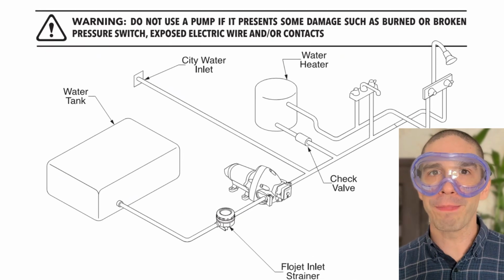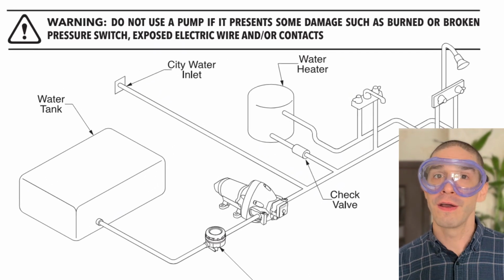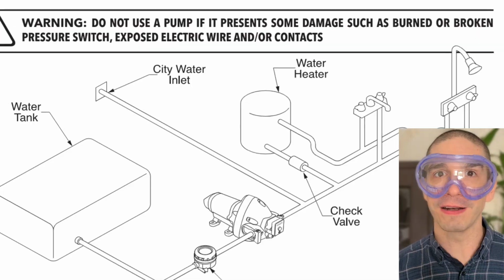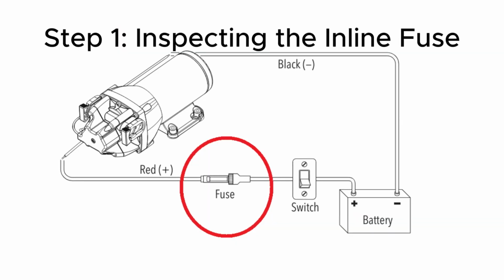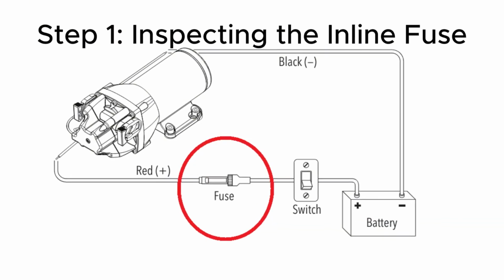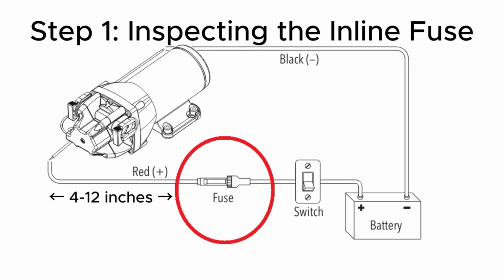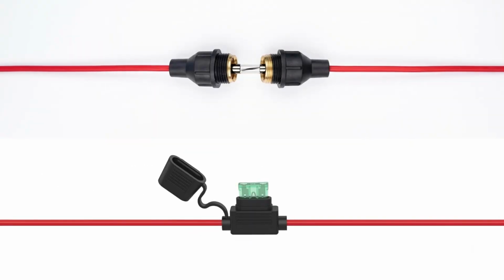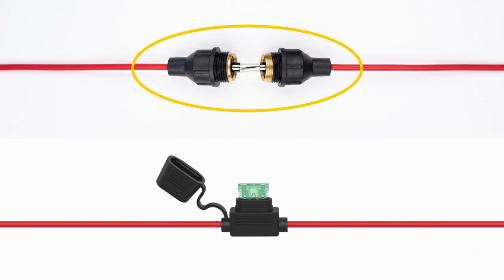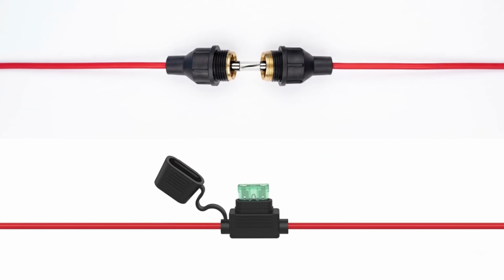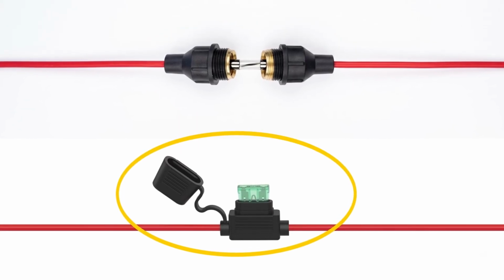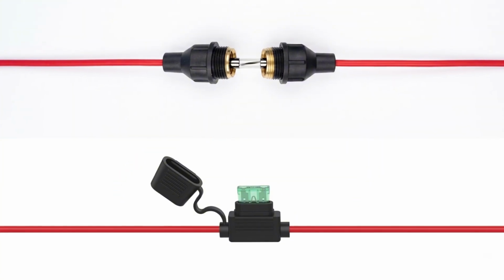If your Flojet pump fails to turn on, first check the factory-specified electrical components. Trace the red positive power wire coming directly out of the motor. About 4 to 12 inches away from the motor, you will find a small plastic cylinder or rectangular fuse holder in line. Twist or pull the plastic capsule housing apart to expose the fuse inside.